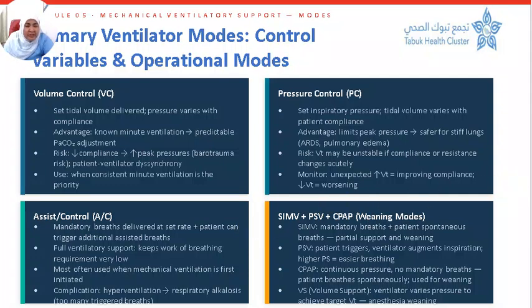So the primary control mode that we are going to discuss is volume control. Volume control means that you can set or control the patient's tidal volume. So with a set tidal volume and a set respiratory rate, there is a known minute ventilation. This is good when it comes to making adjustments to achieve a desired PCO2. One of the negative aspects is that when we use volume control, since the tidal volume is preset, if the patient's lung compliance were to decrease, this could result in high peak pressure. Another drawback of volume control is that the patient might have ventilator dyssynchrony.